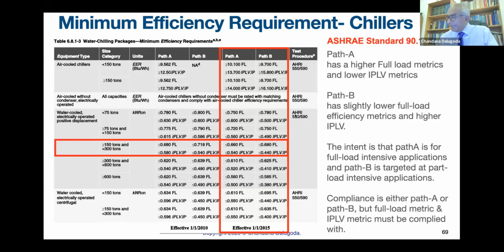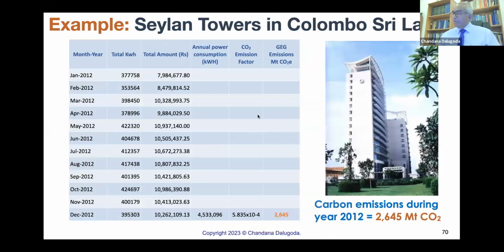Let's say 300 tons, your efficiency at full load should be 0.66 kilowatt per ton. Part load 0.540 kilowatt per ton. That is the minimum efficiency. If you can have even smaller values, the better. So when we are selecting chillers, we don't haphazardly select a chiller for the price, for the make, for the physical size, the weight. No. The efficiency. I'm going to give you a very quick example. This is a case study.